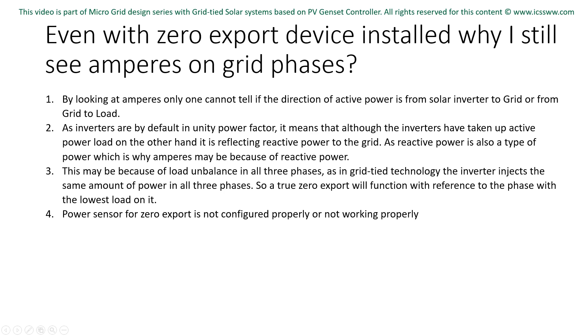Number 3, this may be because of load unbalance in all three phases. As in grid-tied technology, the inverter injects the same amount of power in all three phases, a true zero export will function with reference to the phase with the lowest load on it. Number 4, either the power sensor connected to your inverter is not working properly or it is not configured properly.